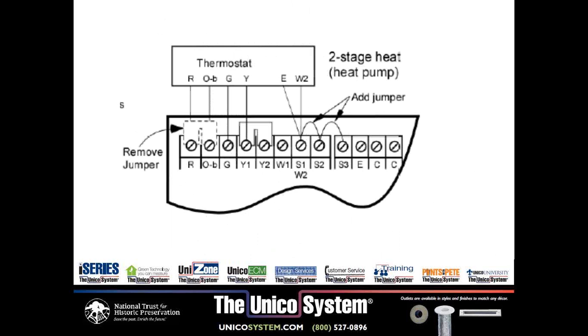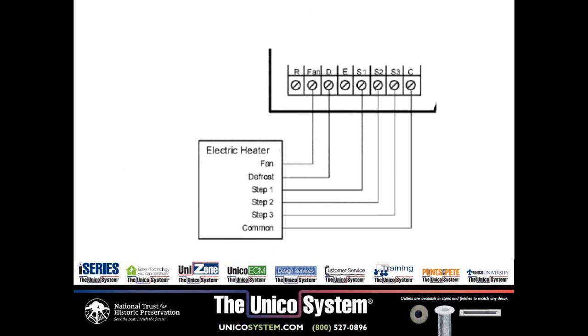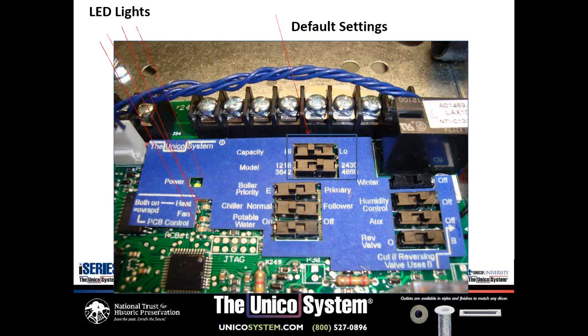So again, these are very simple to do. They're again the same wiring diagram you see elsewhere. This is on our board. This is the control board. If you're using hot water, you notice you have a boiler priority switch. You can set up your hot water coil to be your emergency heat, or in my case, it's set to primary heat.